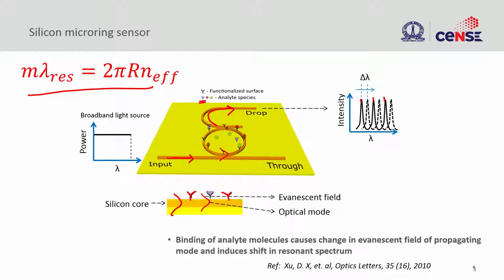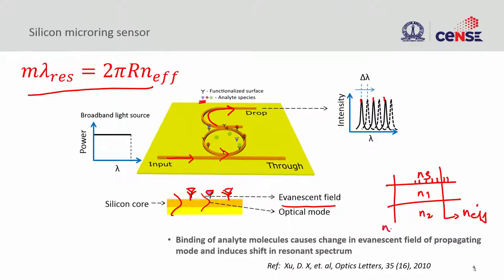You will have lots of analytes, and a particular species will come and sit onto the functionalized surface. When this species binds onto the surface, it will interact with the evanescent mode. Because of this binding, you will have a refractive index change — because the material density around that point is now different. We talked about N1, N2, and N3. There is now a local N3 variation. The N_eff around that point is going to be different. Wherever the molecules are sitting, your refractive index is going to be different, and when the refractive index changes, your resonant wavelength will change — a shift in resonance because of the analytes on the surface.